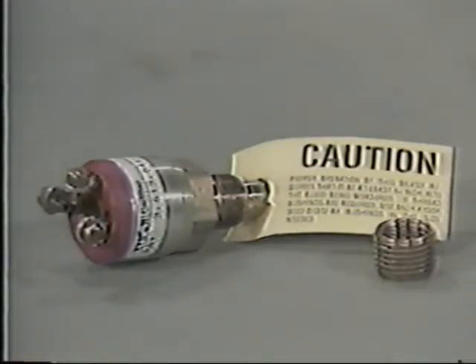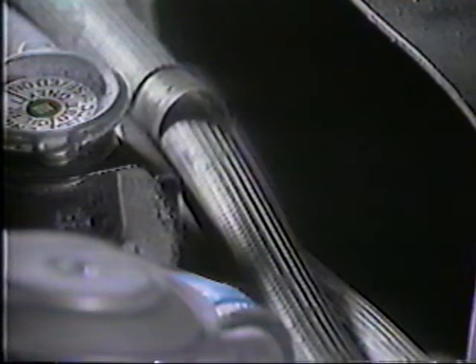Area 5. Alarm and shutdown system alarm stats come with a warning tag concerning reducer bushings, just like alarm-only ones. Failure to follow these instructions may result in a system that does not work. Troubleshooting area 6. Engine cranks but will not start. This is many times traceable to problems in one of 3 module circuits: key switch, ground, and start.